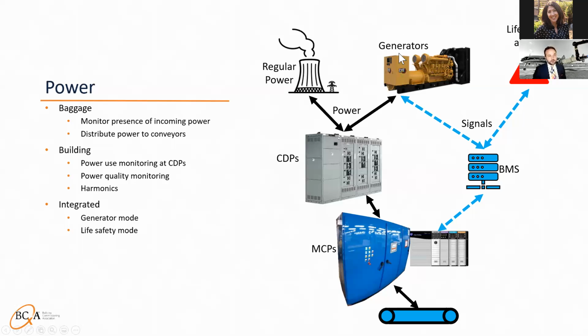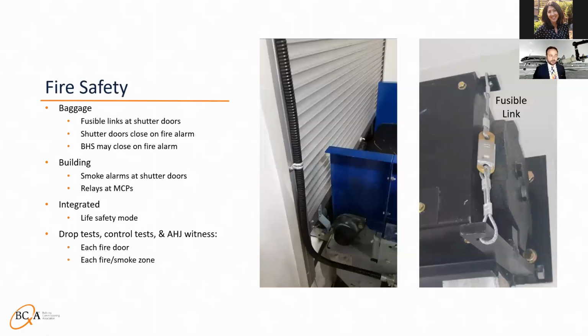Once the building goes into generator mode, a lot of subsystems need to know this, baggage handling being one of them. So the generators will send signals to the building management system, and so will the fire alarm system. That might go to BMS, or you might have relays directly to the baggage handling PLCs. The BMS or the fire alarm system will then send that info to the PLCs, which can then react accordingly. You could theoretically just hit the power on the baggage system and turn everything off automatically, but it's often better to control things, leave things under control so that they can be shut down safely in a controlled fashion, or to maximize safety, such as at fire doors.